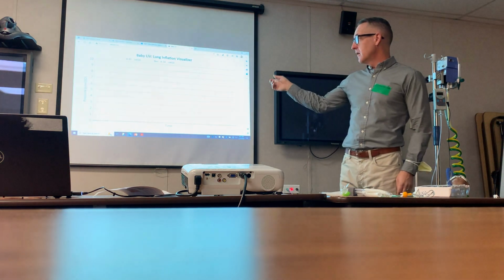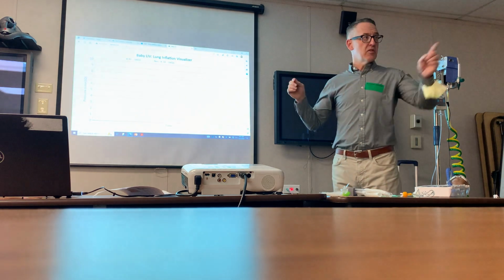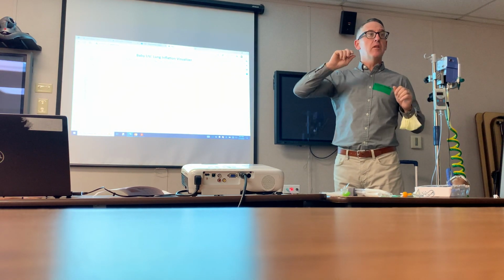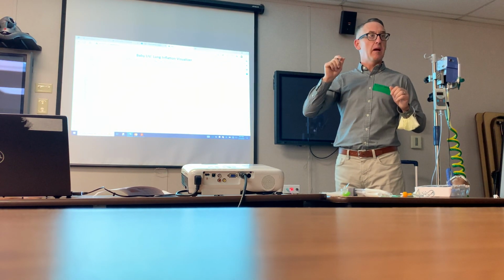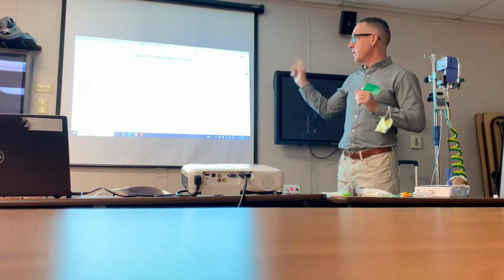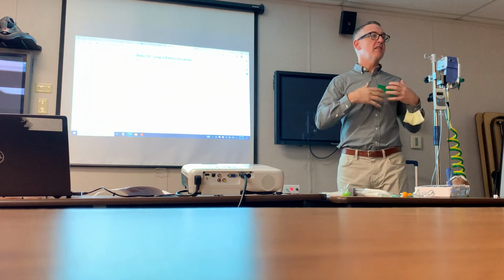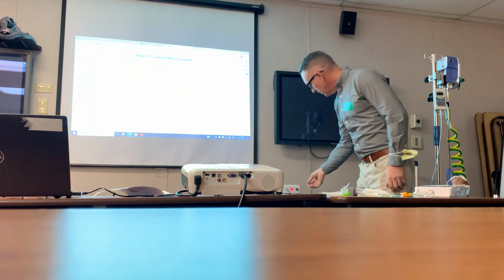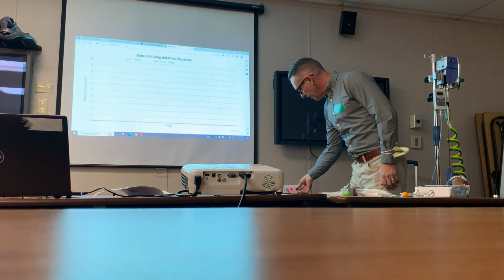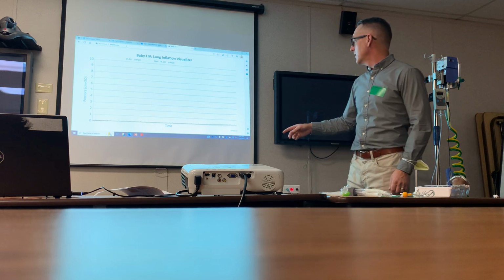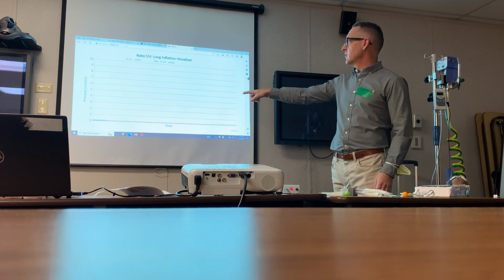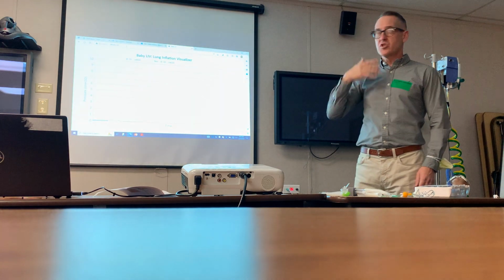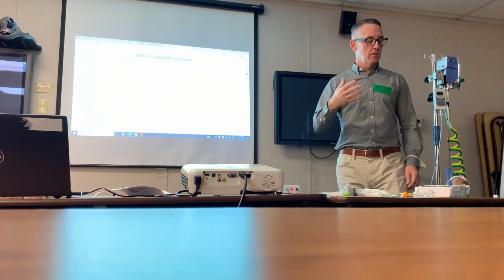Now, to answer the gentleman's question, when the high flow goes up, sometimes you're going to get some CPAP that goes up as well. So we still want to measure CPAP to at least see that we're doing something. So let's increase this to 4 liters of flow. We'll stop off at the minimum. So now we've got a little bit of response. You can see our CPAP is up. We're starting to wash out CO2.